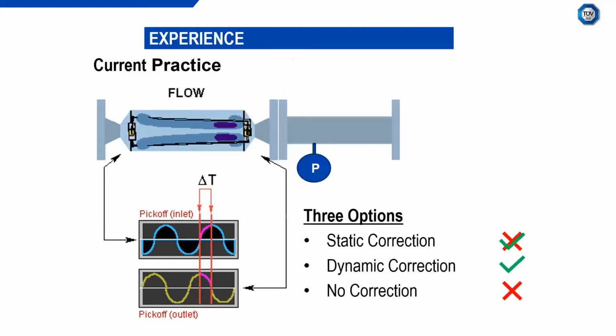If you imagine you're operating in a facility or a process line at 20 bar, it might be 20 bar plus or minus 5 bar. So what correction do you apply? If it's only static, do you apply just purely the 20 bar correction? What about when it's operating at 15 bar gauge, or at 23, 24, 25? The good thing about dynamic correction is that it uses a pressure transmitter, feeds that into the flow computer, and applies an appropriate dynamic correction. We also don't recommend applying no correction. We recommend applying a correction, because pressure effects are significant, and I'm going to show you that in a second.